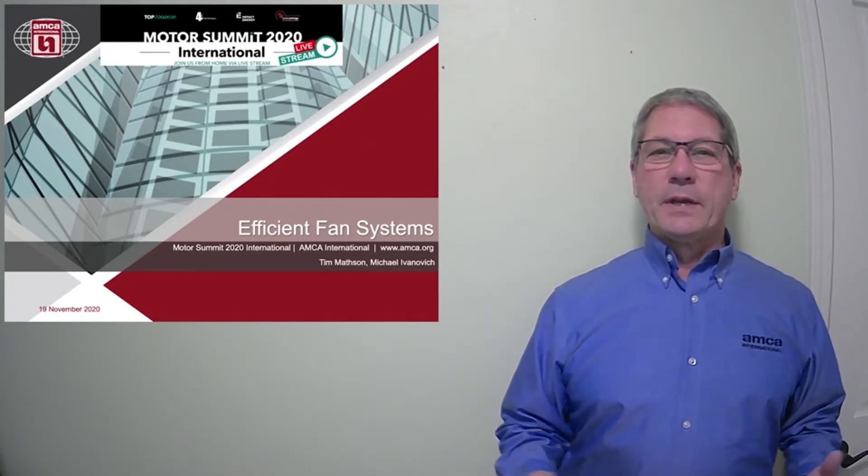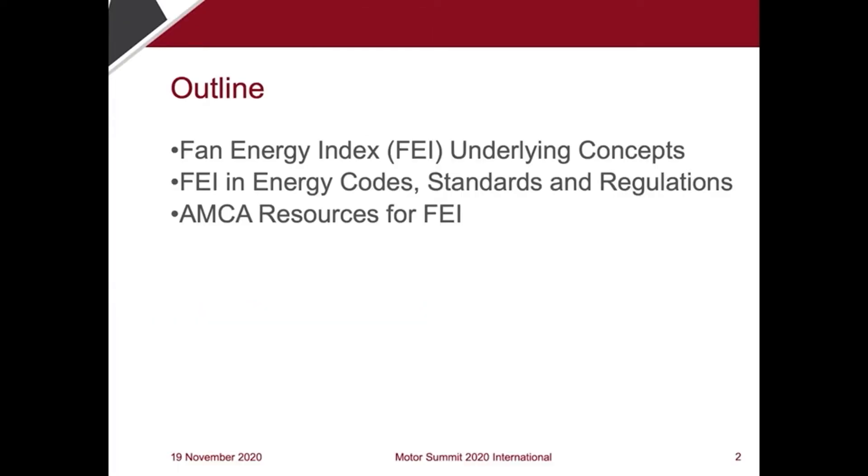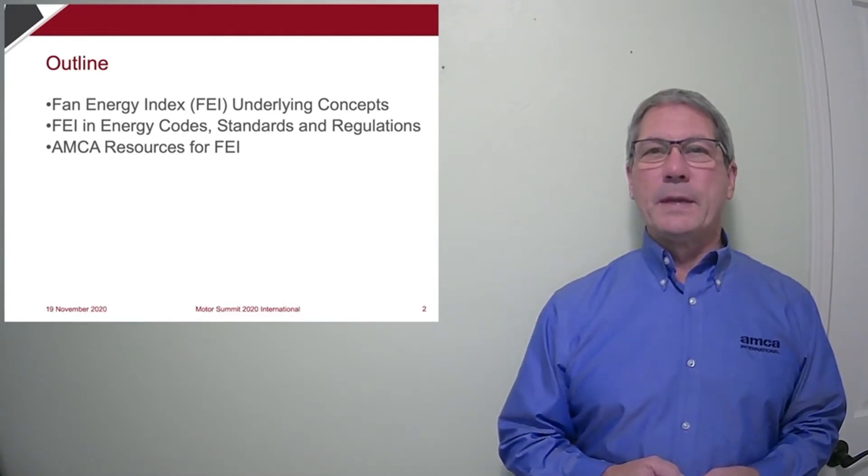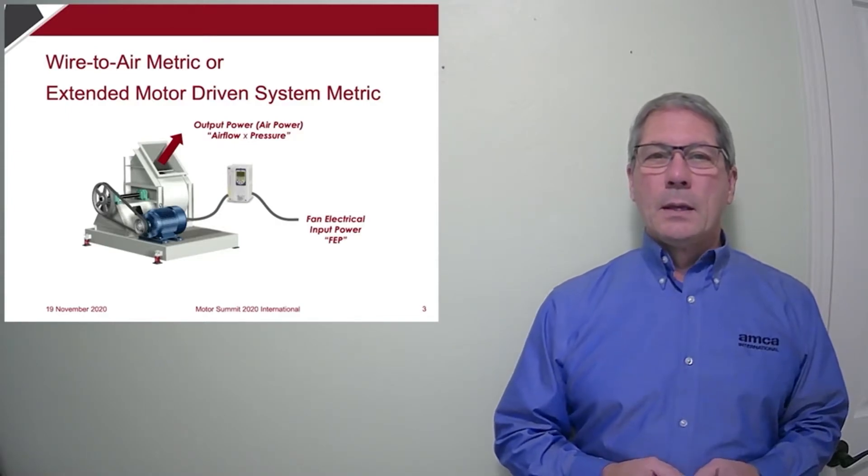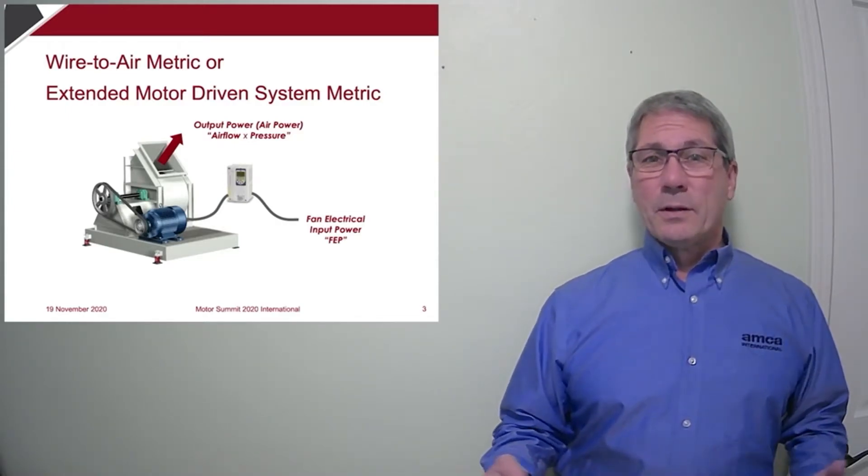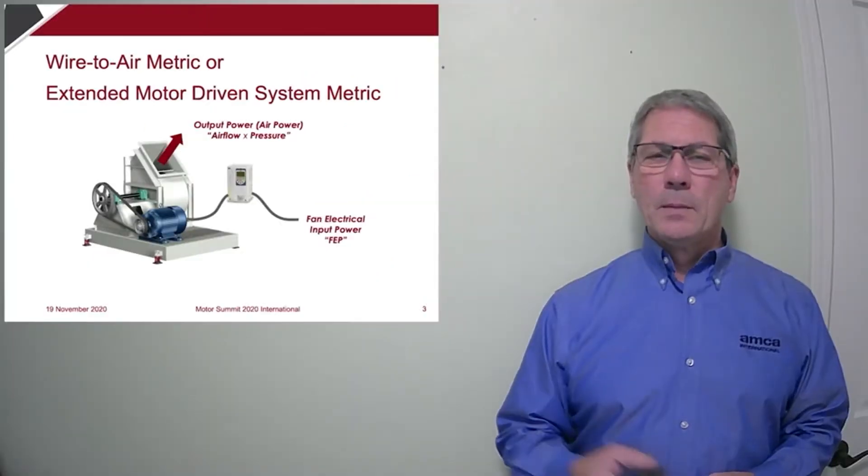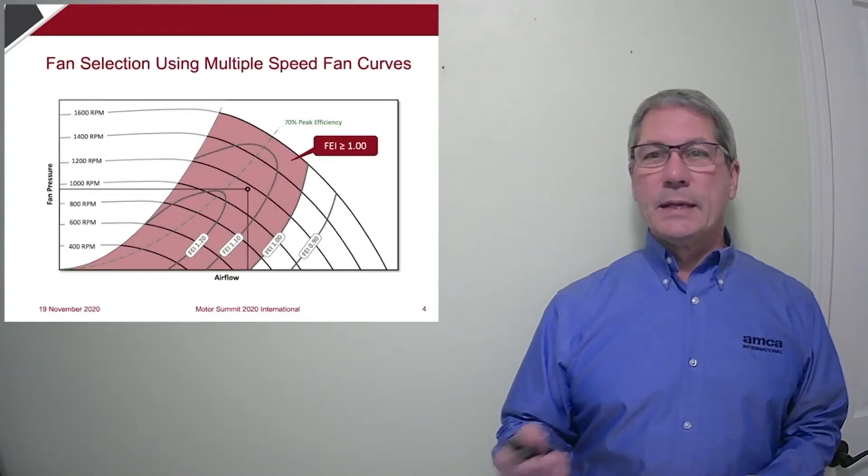We're going to talk about efficient fan systems and how the fan energy index is being used to help save energy. Michael and I have done a number of webinars about how the fan energy index works, but lately we've been asked more about why certain things were done with this metric. So I'll share more about the underlying concepts and some of the reasoning behind it. And then Michael will give a brief update on its use in codes and standards in the U.S. We call the fan energy index a wire-to-air metric. You may call it an EMDS metric. Same concept, just different terms.